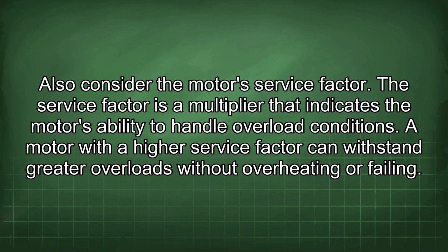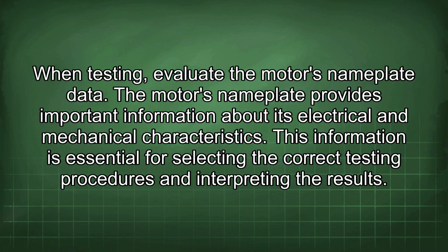Also consider the motor service factor. The service factor is a multiplier that indicates the motor's ability to handle overload conditions. A motor with a higher service factor can withstand greater overloads without overheating or failing. When testing, evaluate the motor's nameplate data. The motor's nameplate provides important information about its electrical and mechanical characteristics. This information is essential for selecting the correct testing procedures and interpreting the results.